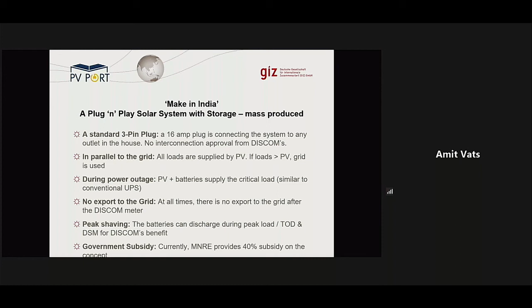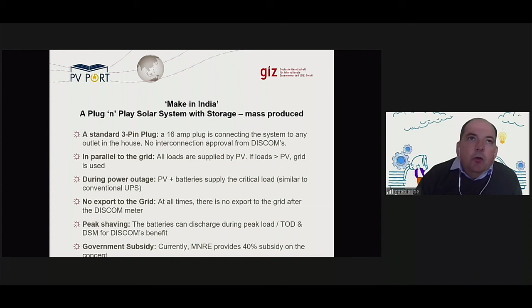We had these parameters to fulfill: UPS functionality, meaning the system takes over the critical load in the house; no export to the grid, so there's no regulation necessary for a battery or solar system feeding into the grid when maintenance is happening; peak shaving to help the DISCOM utility with peak loads; and also being under 3 kilowatt size to obtain the subsidies currently called phase 2, with a maximum of 40%. So we did that.